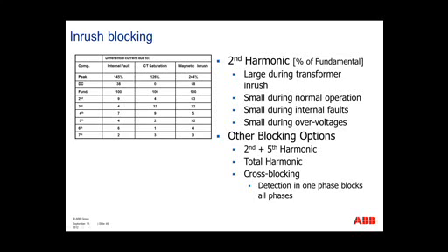Other blocking options that you can have is a total harmonic condition, meaning that all three phases show the characteristics of second harmonics. Another blocking option is cross-blocking. What that means is if one phase detects this second harmonics, it will block all three phases from tripping the differential.